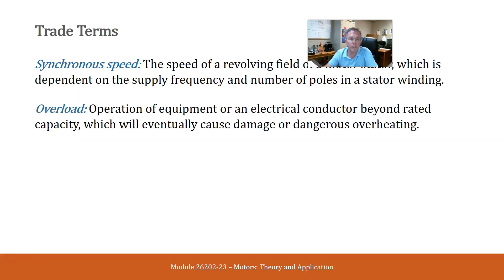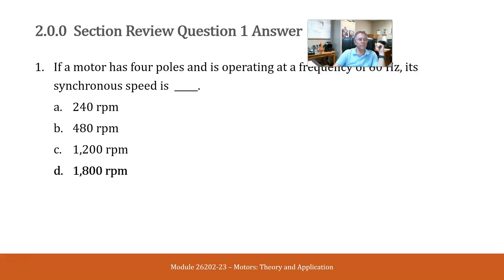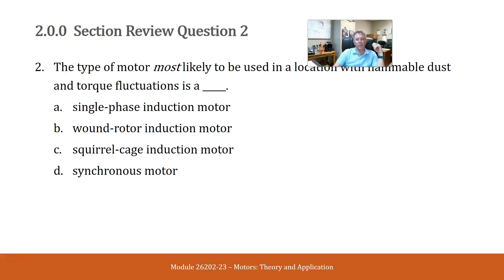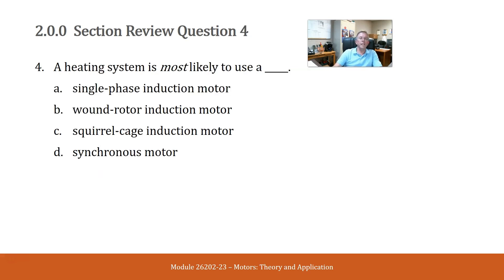Here are some trade terms you should read over and become familiar with for this section, and some review questions. If a motor has four poles and is operating at a frequency of 60 hertz, the synchronous speed — remember this calculation is in your book and we will do them in class — is 1800 RPM. The type of motor most likely to be used in a location where there is flammable dust and torque fluctuations is a squirrel cage induction motor. A type of motor used in precision applications that requires constant speed with zero slip is a synchronous motor. A heating system is most likely to use a single phase induction motor.